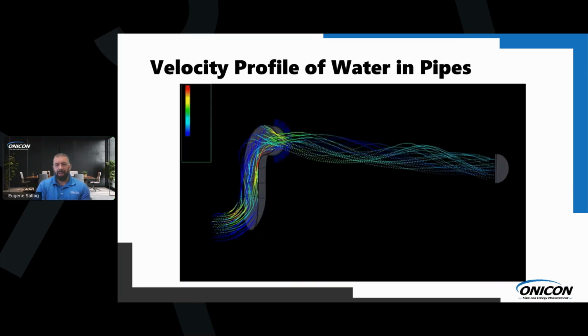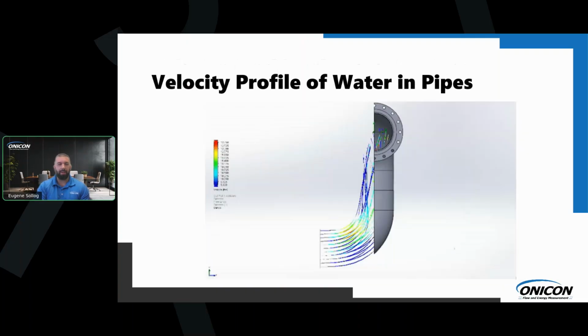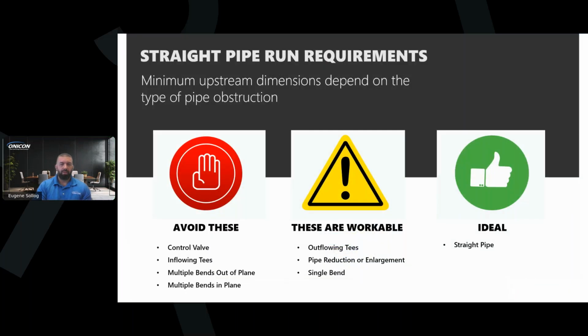These are just some CFD models that we have that show a multiple bend out of plane. So you can see the swirl that's induced in this. It really causes a lot of swirl in the pipe, and it's hard for any flow meter to really read. So for straight run requirements, just as a rule of thumb, we always want to be away from control valves, inflowing tees, and multiple bends in and out of plane. Outflowing tees, pipe reduction or enlargement, and single bends are easily workable, especially with this inline mag meter.